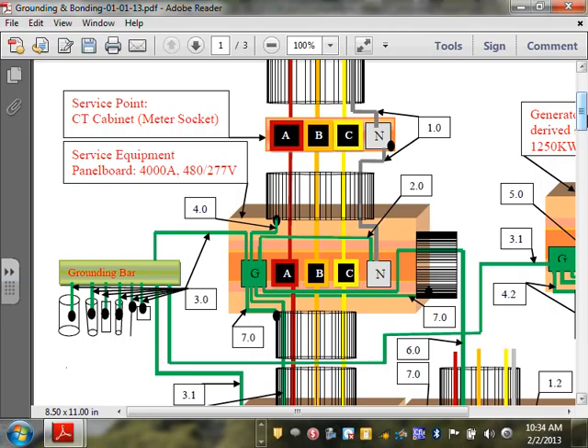Here's number 3. I want to go to number 3. Number 3 is called grounding electrode system. By code, you have to provide at least 1 grounding electrode system, at least. But if that grounding electrode system was a water pipe, you have to supplement it. If it was a rod, you have to supplement it with another. So that's why we end up with 2 anyway. But if you have a concrete encased electrode, you can get away with 1 concrete encased electrode.